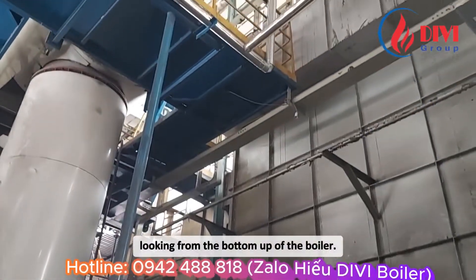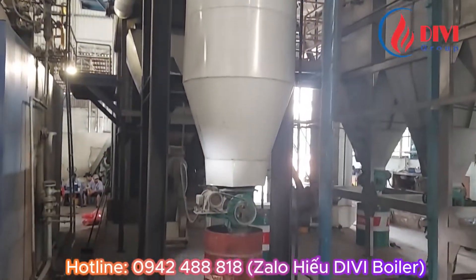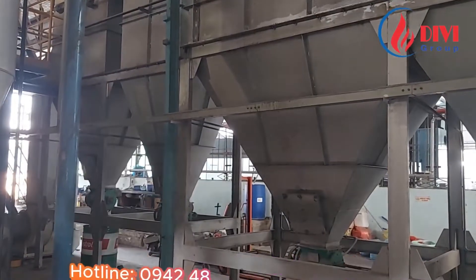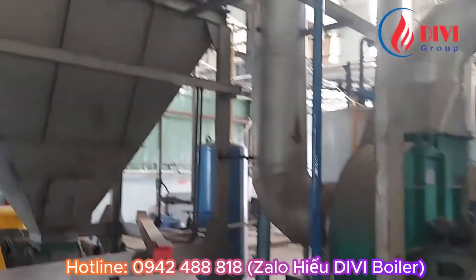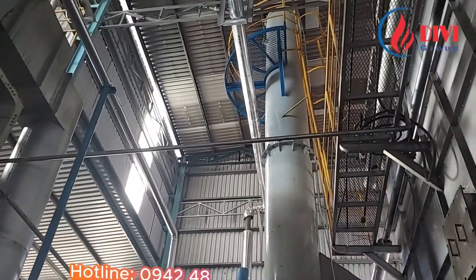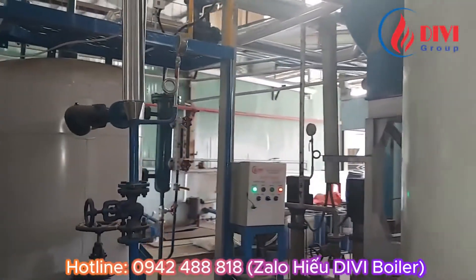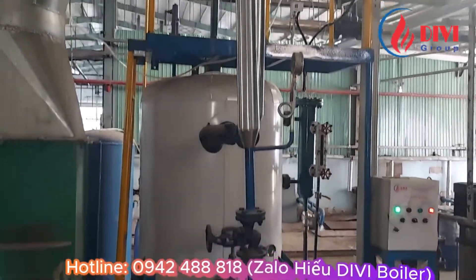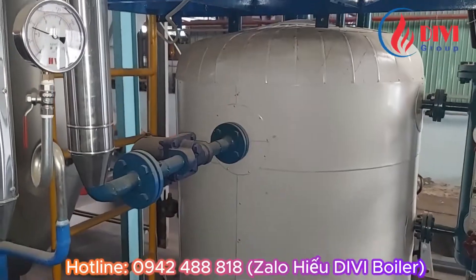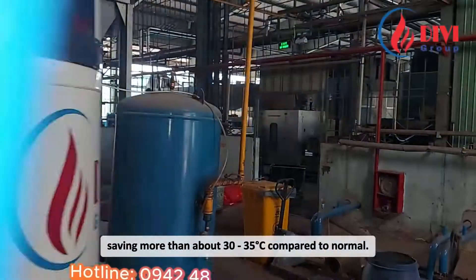This is the back part, looking from the bottom up of the boiler. Here is the ash recovery funnel from the smoke box and the rotary ash removal valve. On this side there are many ash collection hoppers — there are 5 dry ash collection points. This is the smoke extraction fan and the boiler's chimney. Far away is the deaerator introduced earlier, and this is the back of the boiler's economizer. The condensate water tank normally keeps water at temperatures from 90 to 95°C, but with this economizer, the condensate water will be kept at about 130°C, saving more than about 30 to 35°C compared to normal.